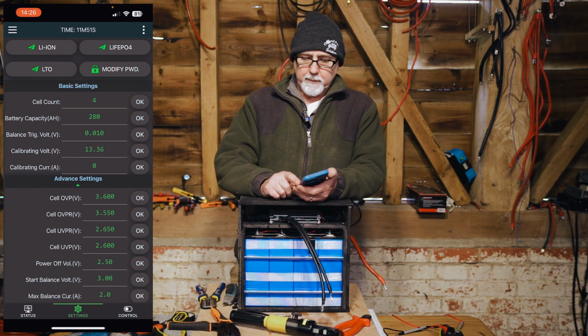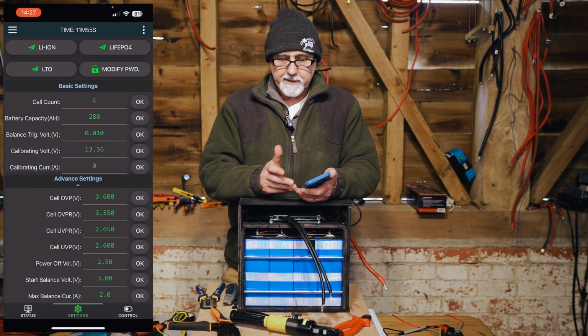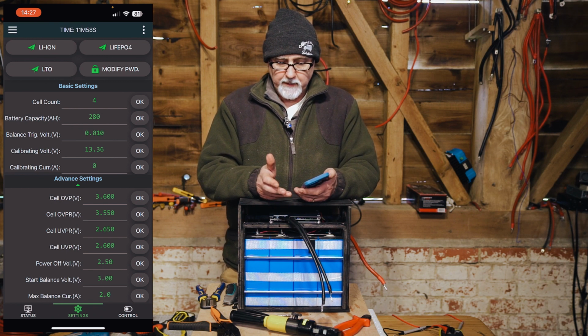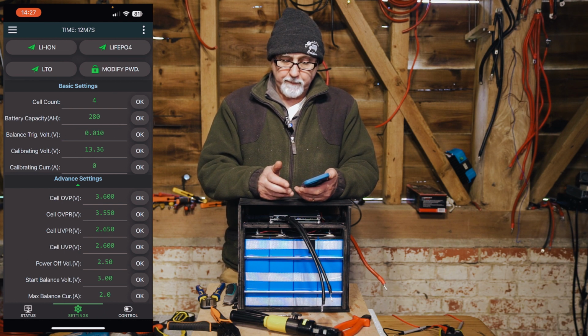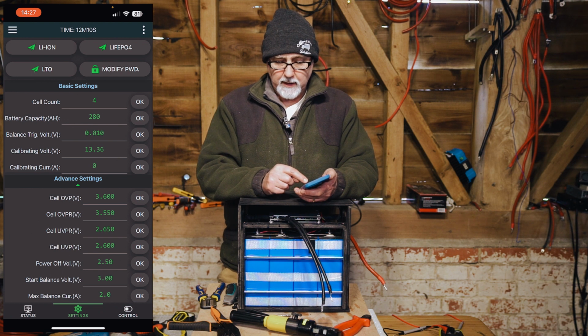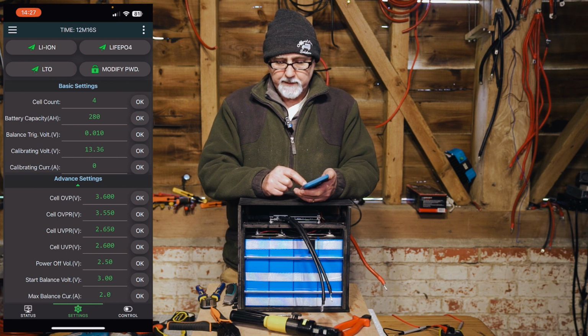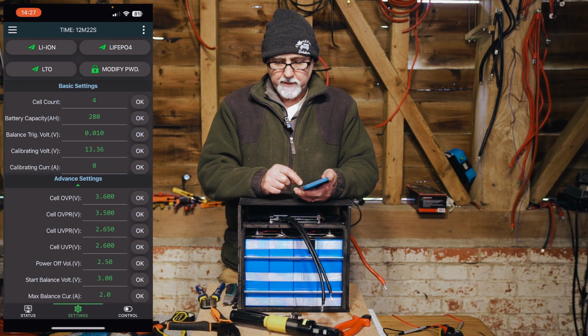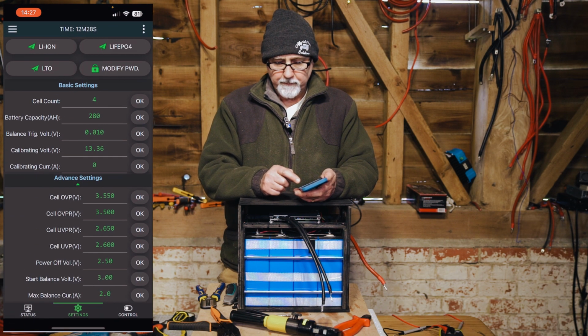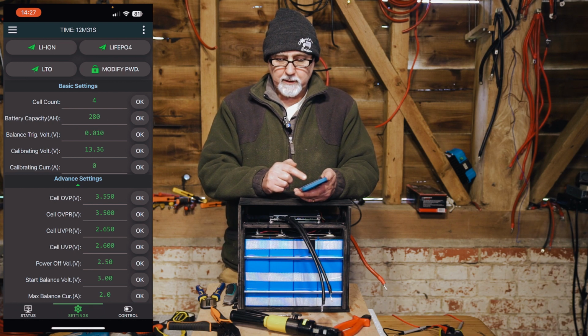Let's run through the settings from the top and configure this for default Victron. The Victron bulk or absorption voltage is usually 14.2, which divided by 4 is 3.55. So we need to change the overvoltage protection reset and the overvoltage protection. We have to change the reset first, so let's set that to 3.5. Now we can change the overvoltage protection to 3.55, which makes it immediately compatible with Victron charge defaults.